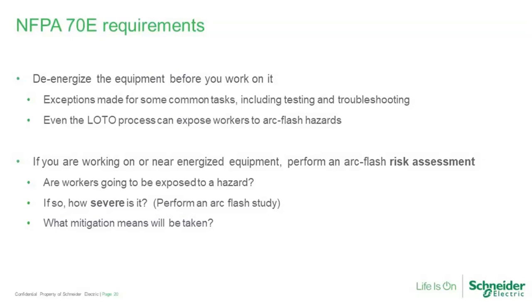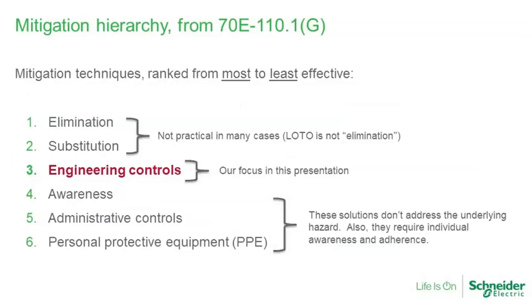OSHA 1910.269 was revised a few years back. It's 2015 or 2016, I don't remember exactly which one now, but the specifics in the requirements are a little bit different than what is contained in NFPA 70E, which would apply mostly to commercial or industrial facilities. But I think in a lot of ways they're very similar. Even if the details don't line up exactly, OSHA gives the idea that if a worker is going to be exposed to hazardous energy, you need to go through the process of performing a risk assessment. You need to go through the process of estimating the incident energy to figure out how bad the exposure would actually be, and then it talks again about providing appropriate protection and mitigation means to those workers in order to reduce the risk. So again, regardless of what kind of system you're dealing with, we've got some of the same concerns and same things that we look at to try to deal with the problem.